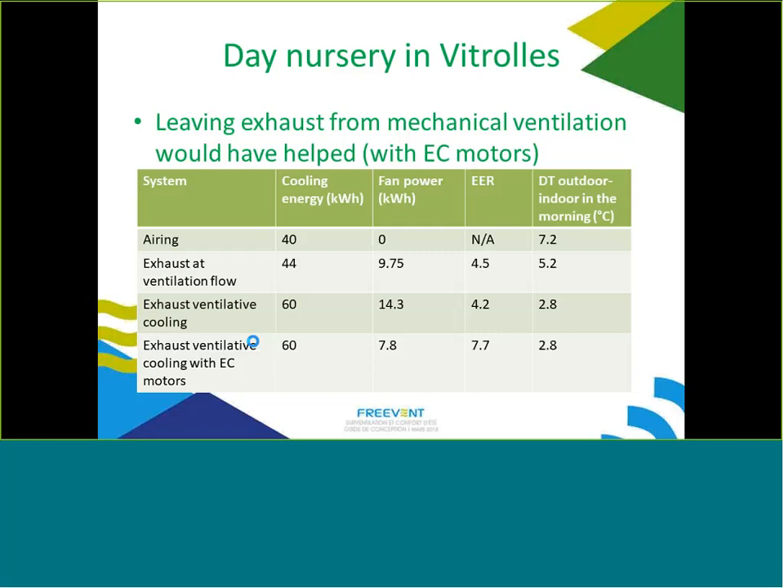One easy improvement would have been to keep the mechanical exhaust running at night, which would help air transfer since exhaust exists in all rooms and would supplement the insufficient natural ventilation. Simulations show: today with airing only, cooling energy is 40 and EER is infinite since there is no fan power, but the morning delta-T is still 7°C. Keeping only the ventilation flow could decrease temperature by 2°C; increasing airflow further could achieve 3°C or more. However, using EC motors gives both better EER and greater temperature reduction, potentially avoiding or reducing air conditioning use.